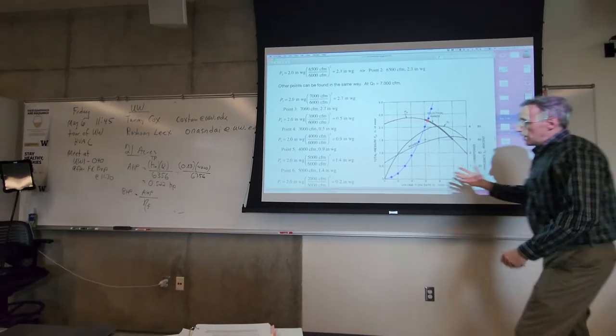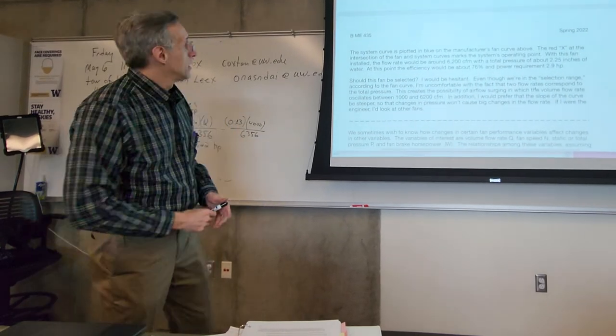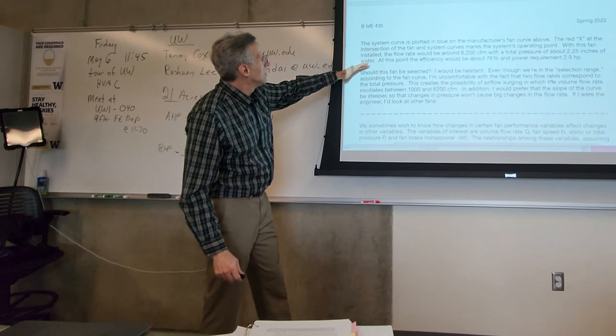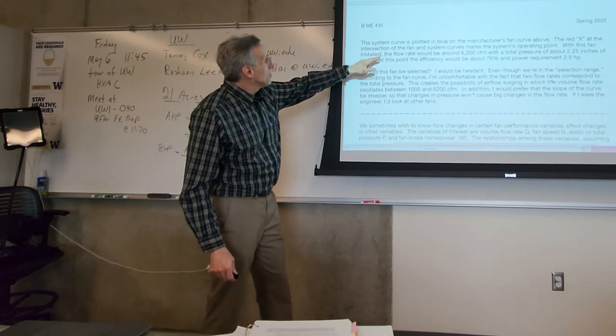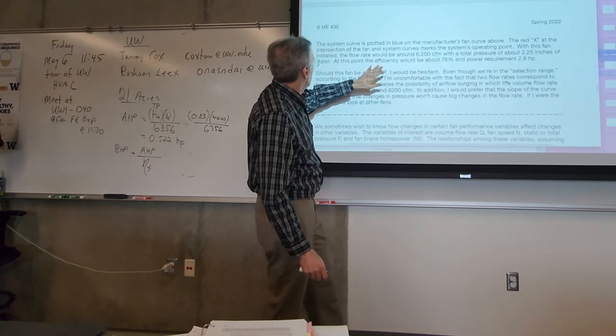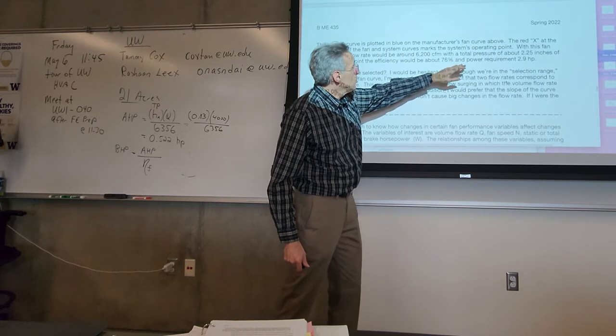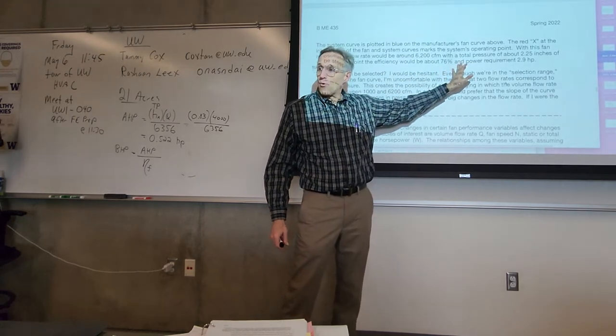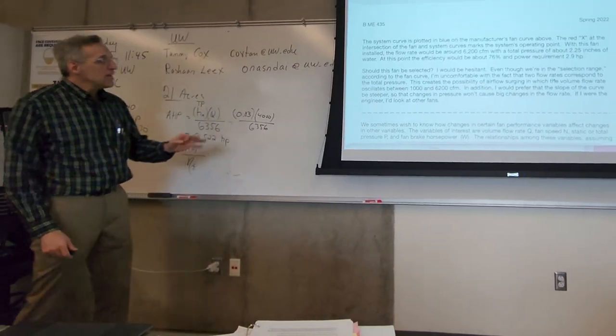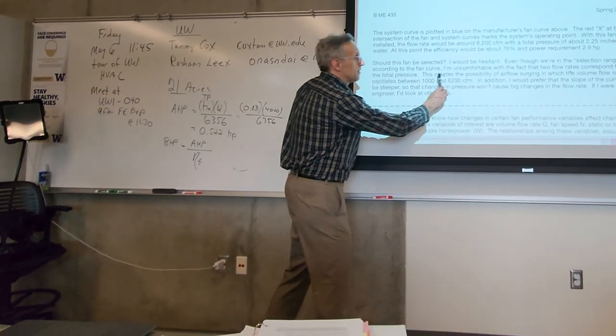Okay, now we come to the end of this. So I've got my system curve, and with the fan installed, the flow rate would be about 6,200 CFM, 2.25 inches of water, and 76% efficient, 2.9 brake horsepower at the design point. Should I be satisfied with that? And I say here, I don't know. I don't think I would be.